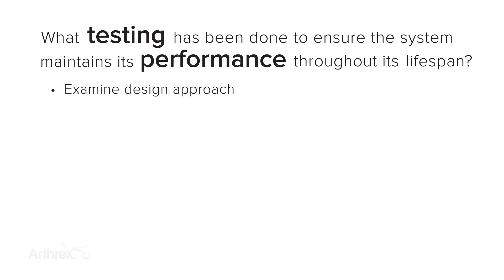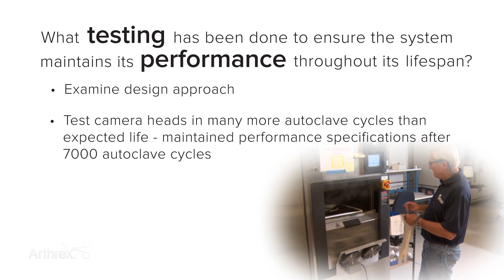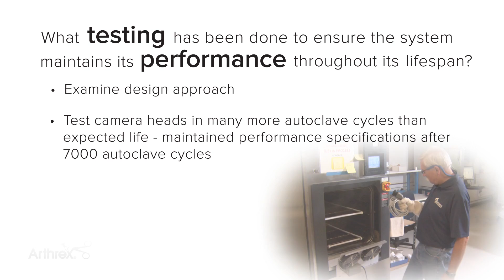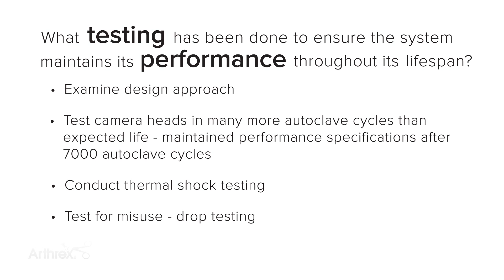The testing that we've done to ensure that the system maintains its performance through its life after many autoclaves, the first step there is our design approach. We run autoclave cycles that are significantly longer than the expected life of the 4K camera heads to ensure the systems and the manufacturing techniques are robust to many autoclaves. In addition to extended autoclave testing, we do thermal shock testing, which is not necessarily consistent with typical hospital use, but it's a worst case test. We also test for even misuse of the device in the field.